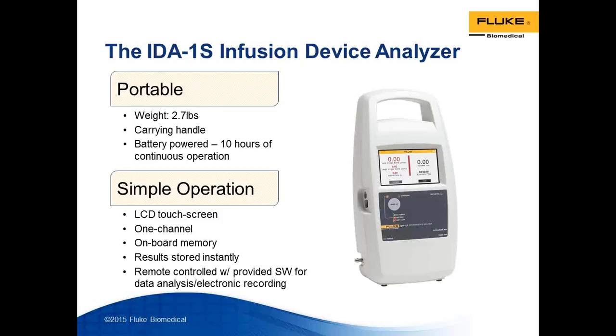One is that for those users who would like to still use this for benchtop testing, they can connect the analyzer to a PC and drive it through our software. The software is free of cost, it's included with the product. So you don't ever have to touch the analyzer if you don't want to. And it has a lot of other features like creating trumpet curves, and a lot of graphical visual depictions of the data. So that's one unique feature of it.